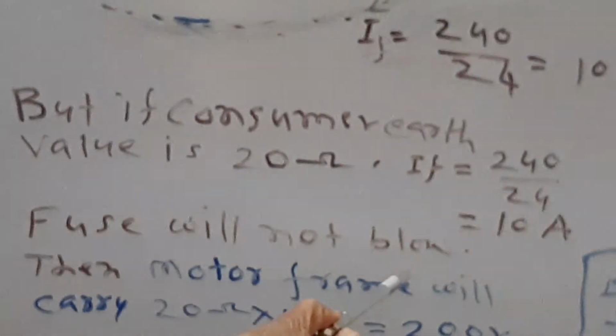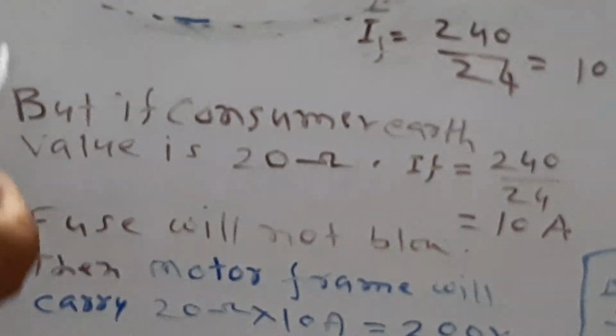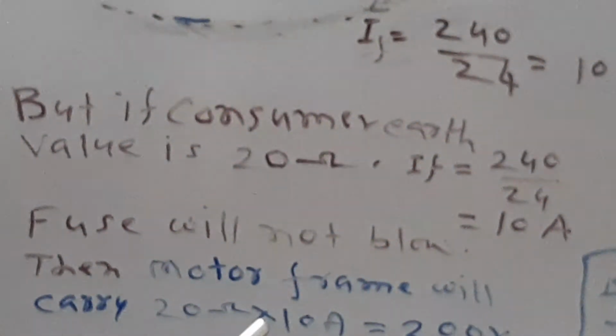This 200 volt will be the voltage of the metallic frame, and when this person touches this motor, the voltage across him will be 200 volt, and he will get electrocuted. This is one case. But had the value of the motor earthing been much less than 20 ohm and the neutral earthing less than 1 ohm, the fault current would have been very much more, that is more than 20 to 25 amperes, and in that case the fuse would have blown, and before the person touched the frame of the motor, it would have been isolated from the circuit. I think I have made this matter very clear. In case of any doubt, kindly contact me.